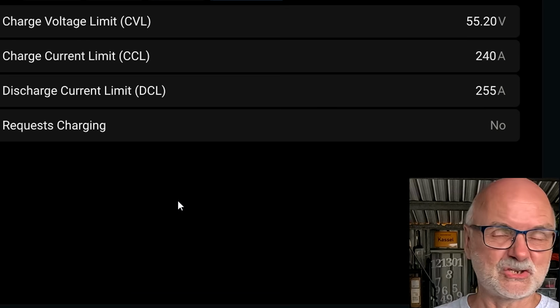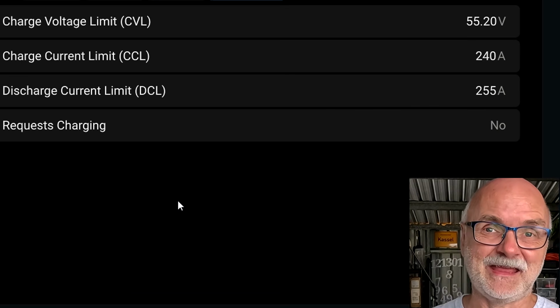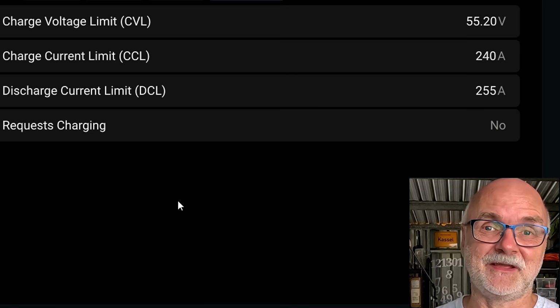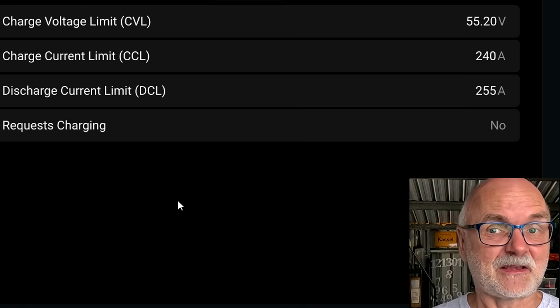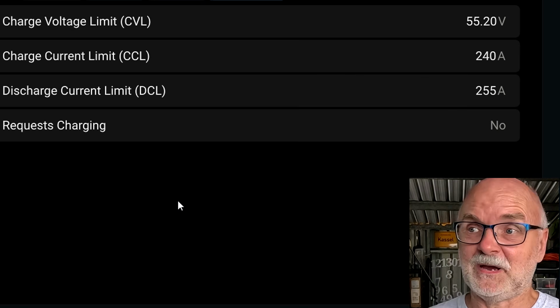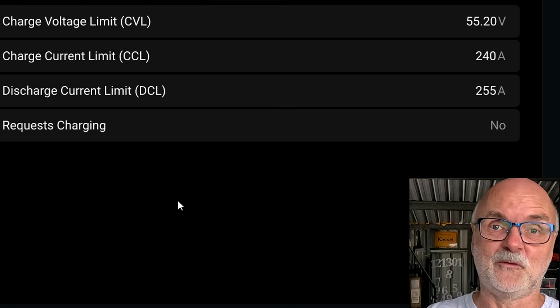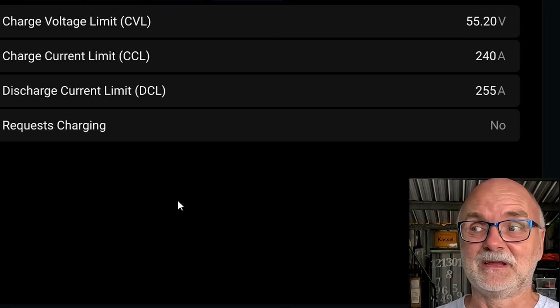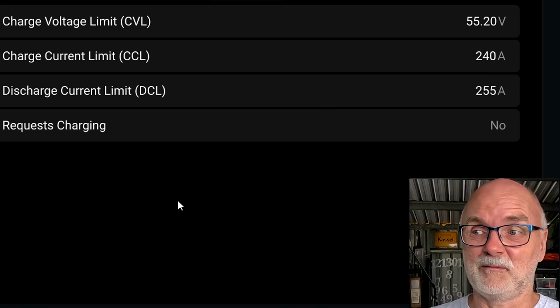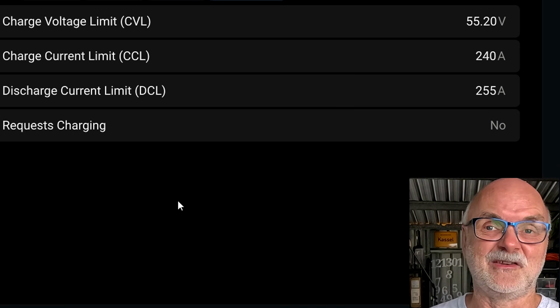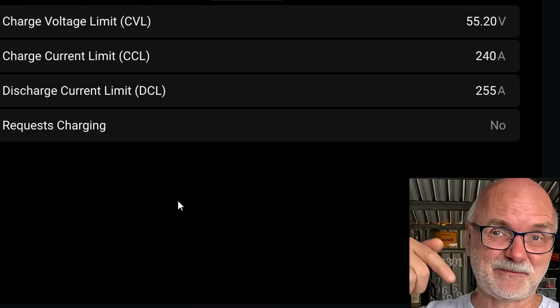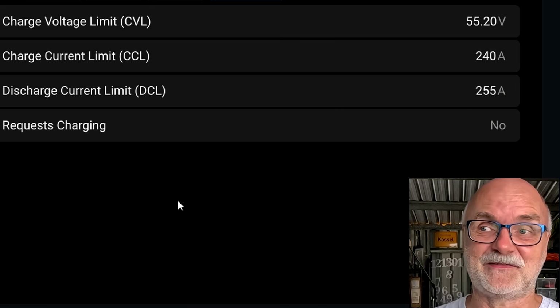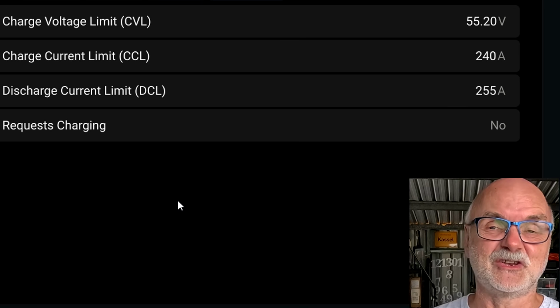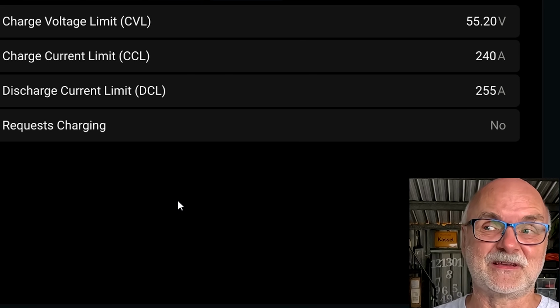It is not responding anymore. It is stale, an issue with the firmware. It is just hanging, not responding, not communicating anymore. But it is still connected and it is still charging. But the master BMS or your inverter does not know anything about it. So we are charging up our system a little bit slower than before, but we don't get an alarm, so we are not getting notified. And in this battery, which has a faulty BMS, a stale BMS, we are still charging it because the charge MOSFETs are still on.